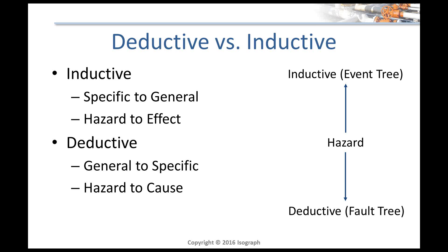Contrast this with a deductive analysis method: deductive reasoning is the opposite, where you start with a general observation and work your way to specific causes. In failure analysis, that means you start with your general hazard or failure mode and then work backwards to individual specific causes that could create that hazardous condition. That relates to fault tree analysis, in which you start with the top event and work your way backwards to figure out the individual failure modes of components that could lead to that hazardous occurrence.